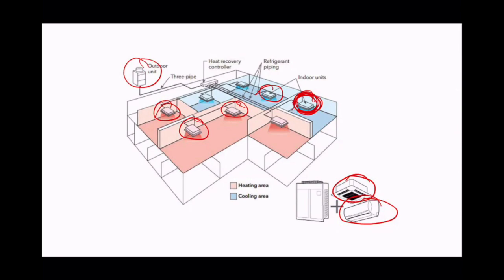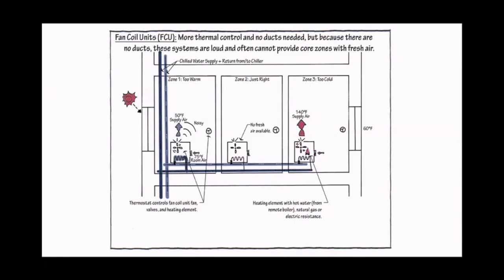Now people get confused between mini split, VRF, or multi-split systems on one side, and a fan coil unit on the other, because a fan coil unit also has a thermostat in the space, also has a fan in the space, and is also blowing room air over a local coil. By local, it could be in the closet, on the wall, on the ground in the corner, above the ceiling, or even in another room and be ducted over. But typically it's in the room in the case of fan coil units.